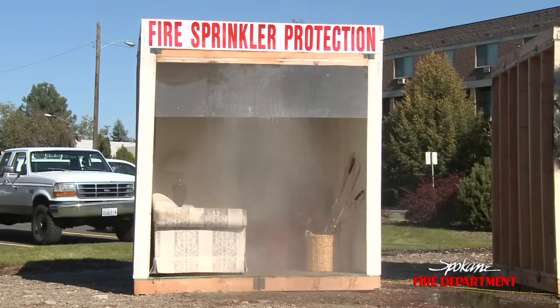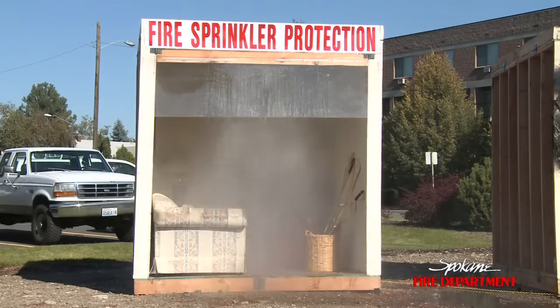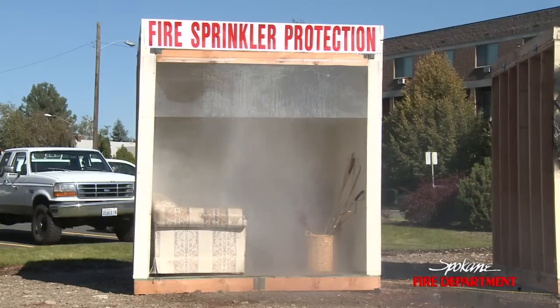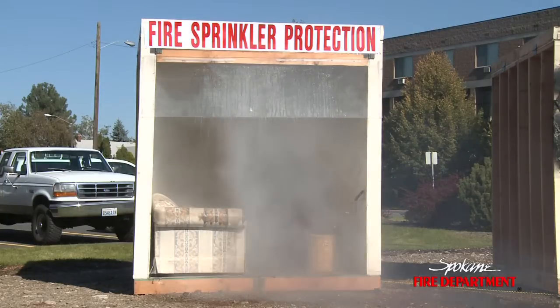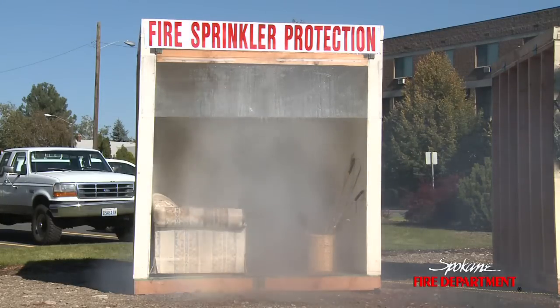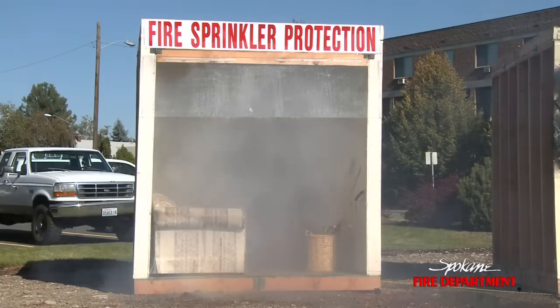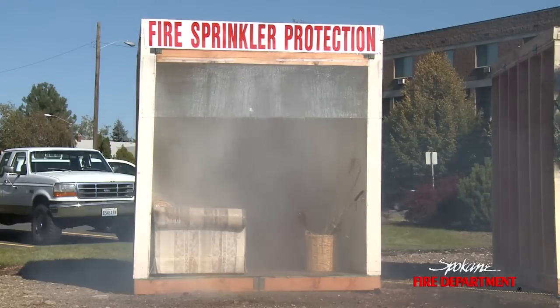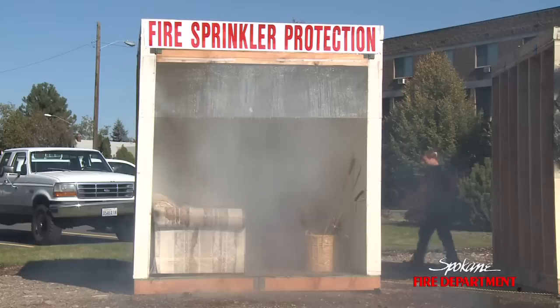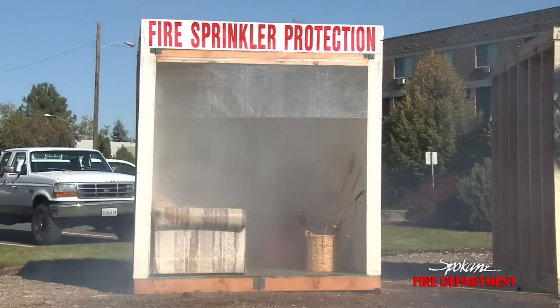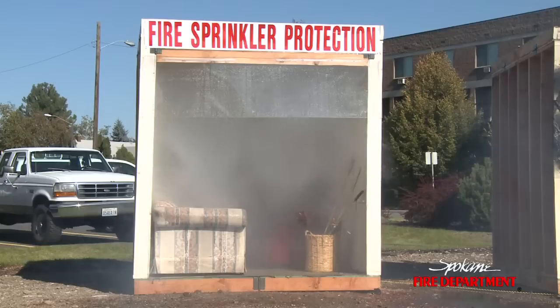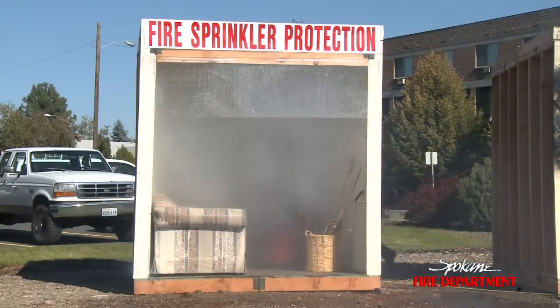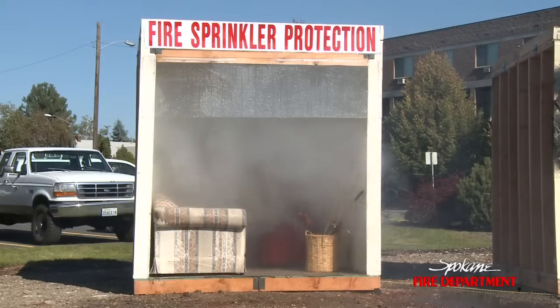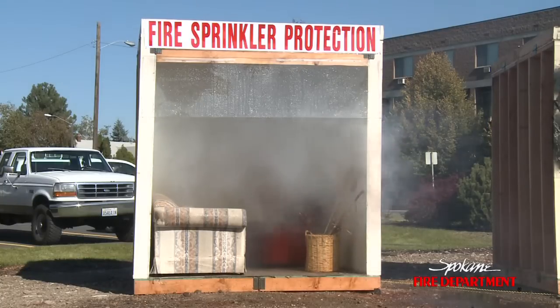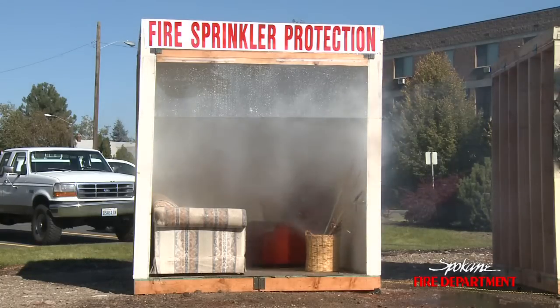You see how quickly that activated. There was virtually very little fire in that room at all. The temperature did not get much above 100 degrees. And it went off in about 50 seconds from the time the fire started burning in there. So we'll go ahead and shut down the flow to that sprinkler head. We'll just let it flow for a minute to make sure that the fire is out. Typically, what would happen is once that activates, it would continue to flow water until the fire department is on the scene, makes sure the fire is out, and then turns off the sprinkler system.